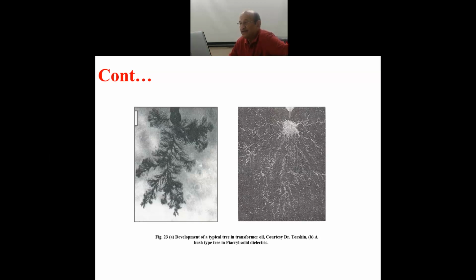Pilling, and you see the similarity in liquid and in solid, in an extremely non-uniform field. The tree formation in the liquid is not permanent because it will be replaced by the oil, whereas in the solid, it will be a permanent feature because of the conductive channels. The tree is nothing but the formation of conductive channels.